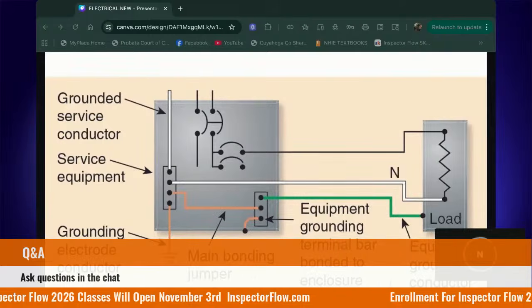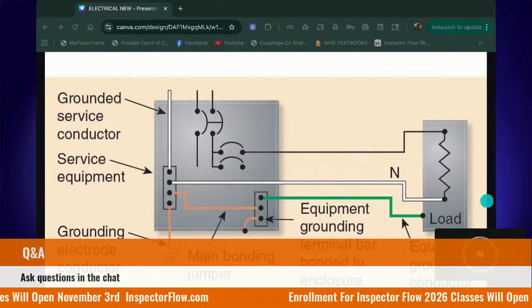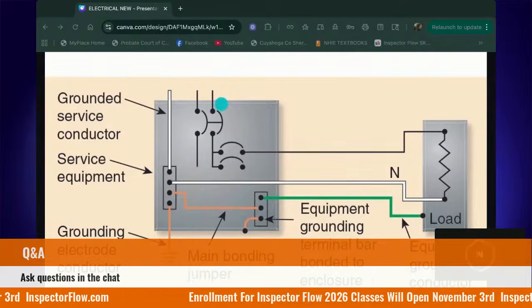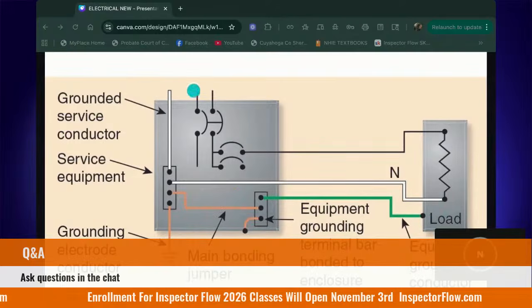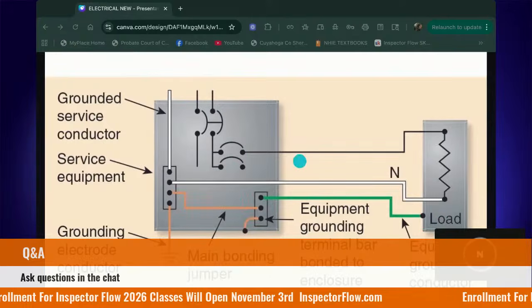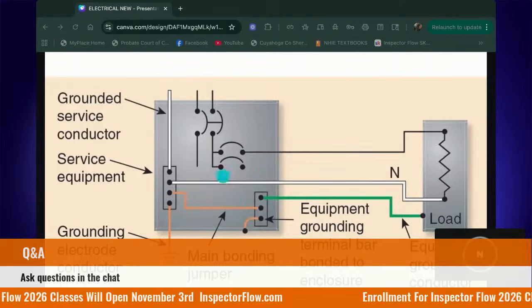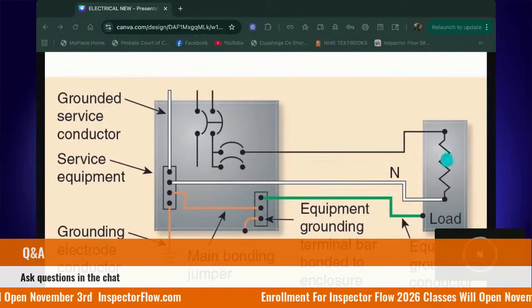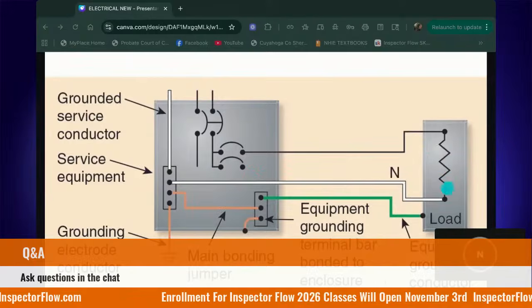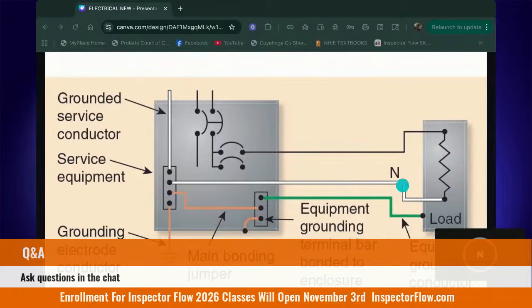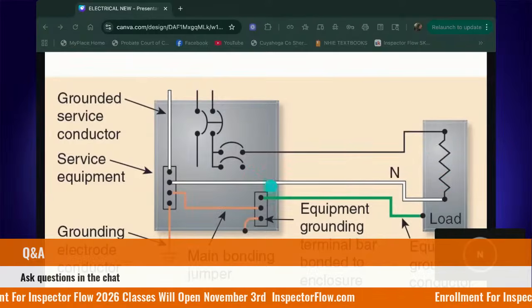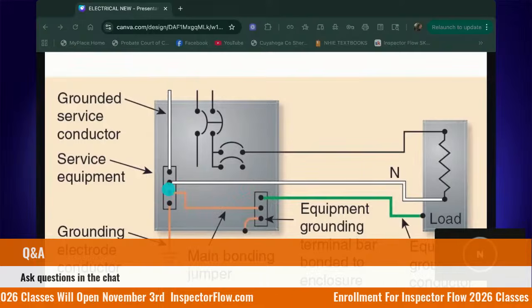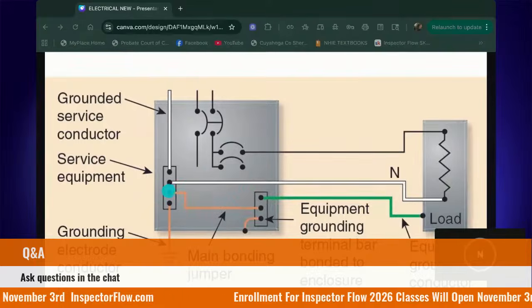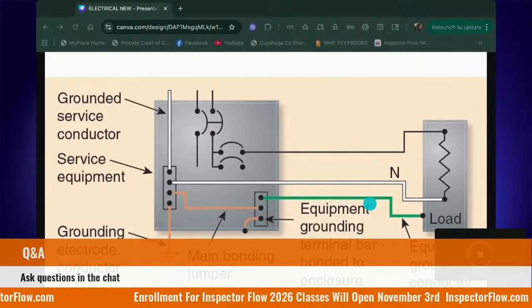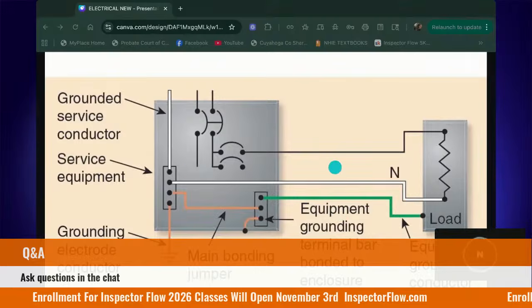Does this make sense? The neutral carries normal return current. This is our normal path. We got our 2 hots coming in, our breakers, our branch circuits, out to the load, power it, boom, the light turns on. Okay, now it wants to go back home. I'm traveling on the neutral, no problem. I terminate here, boom, we transfer, terminate, I'm back to the source under normal operations.